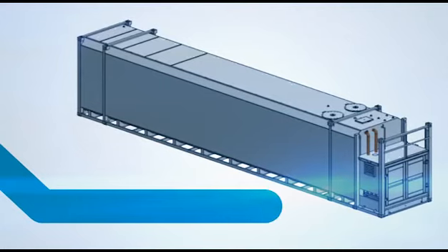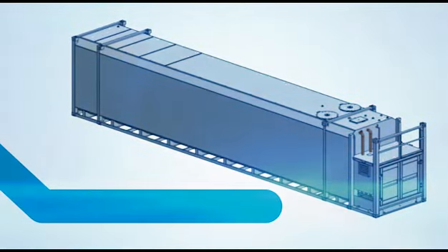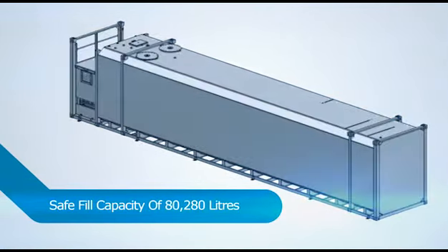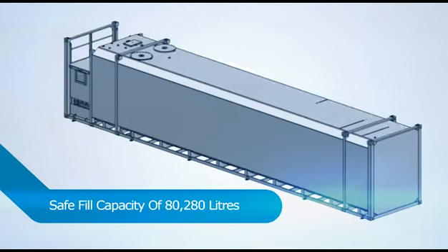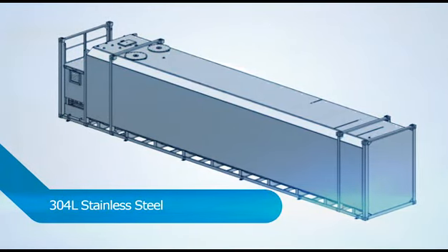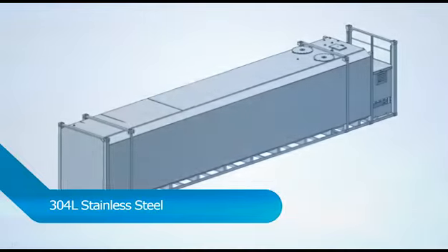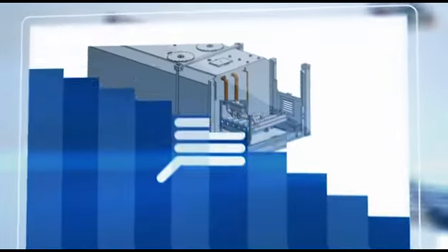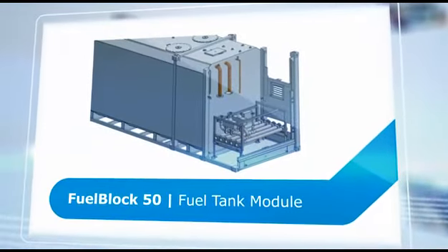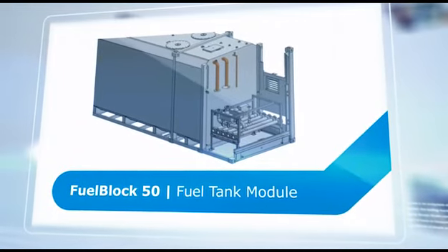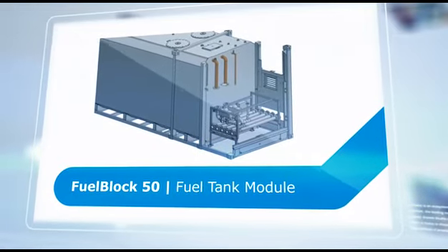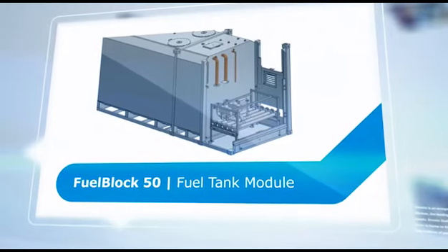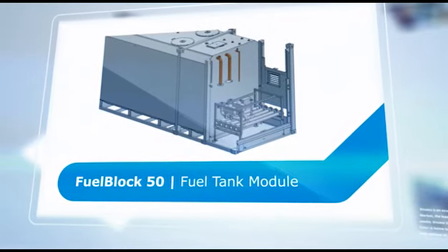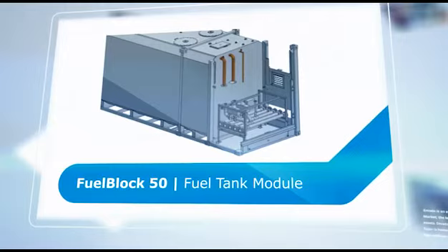The fuel tanks are a self-bunded double-wall design with a safe fill capacity of 80,280 litres. All internal plates and members are 304L stainless steel. Pre-assembled modules complete with piping and actuated valves are installed in the fuel tank valve bay. Level instrumentation is fitted to the tank and easily connected to pre-wired sockets at the module's terminal box.